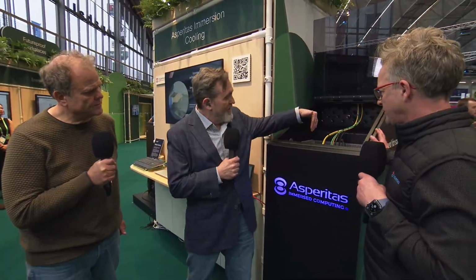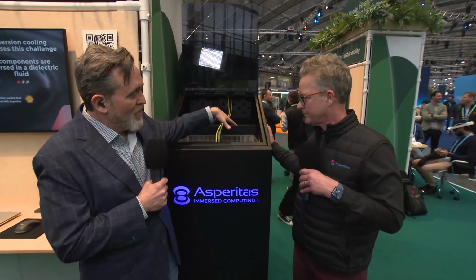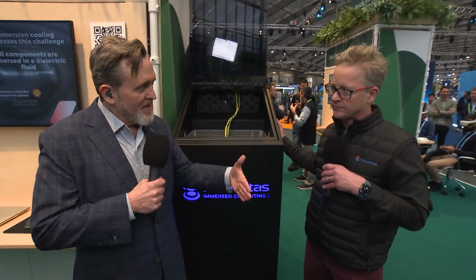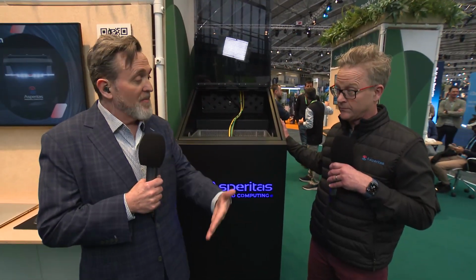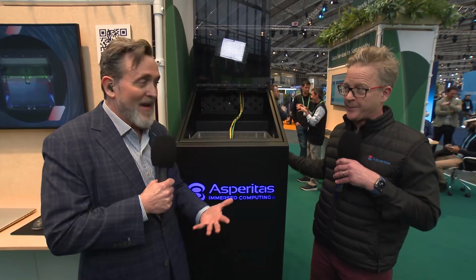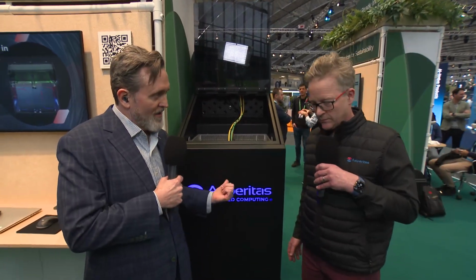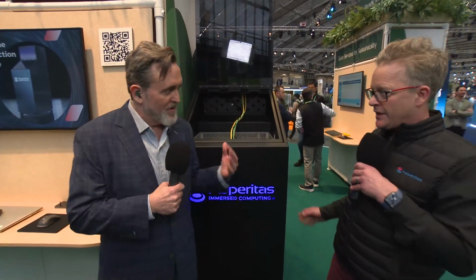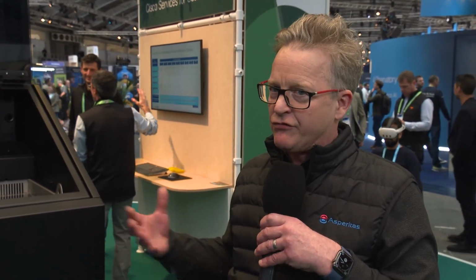I'd like to ask you guys a question - I'll direct it to you, Andy. I notice you just have one device here with a lot of liquid around it. What type of density are we able to get with this? Is it similar to how we're packing racks and running out of space, and now we're controlling it better? How does that work, what's the ratio? Well, really, when you're cooling by immersion, everything gets cooled by a liquid, so you don't have to route pipes to individual high-power components because the liquid's everywhere - it wets the whole server.